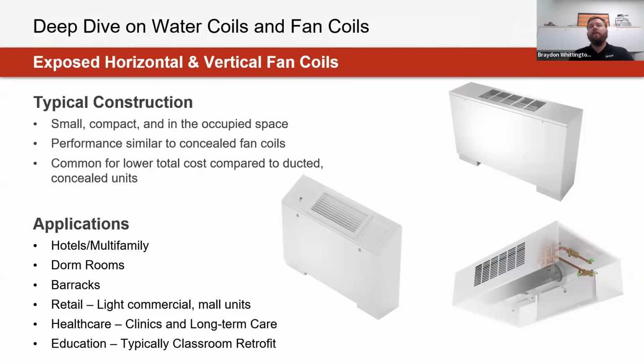So if any of you are running into instances where ceiling space is at a premium, as you see these projects come up and maybe you're running into issues with sizing of equipment, trying to fit it within the space, we can look at different options of potentially playing around with overall sizes, or with where those enclosures or shrouds are positioned on the product, to save on access points or when you're setting them up within your BIM or Revit files as well. So there is some customizability if you're running into footprint struggles. So feel free to bring those up whenever they come up with Airflow and our team here.